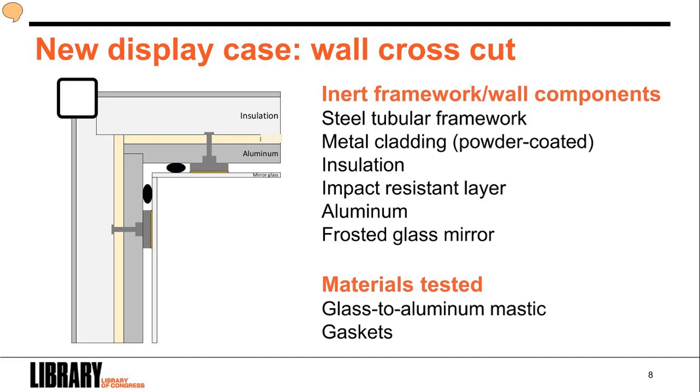I won't dwell on case materials or construction techniques. The point to make here is that we gave thought to the risk presented by a closed air circulation loop within a tightly sealed case. Choosing and testing construction materials was of paramount concern. Again, the modern design, featuring mostly metal and glass surfaces, worked in our favor. Testing proved that the adhesive holding the glass to the aluminum structure posed no concern. However, we reviewed and tested several gaskets before finding an acceptable product.